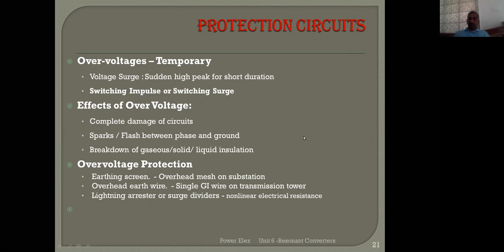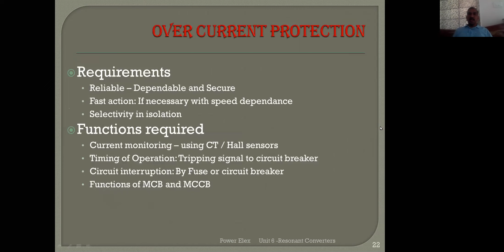The easier ways to protect are having an earthing screen, surge arresters, surge suppressors, lightning arresters, and an overhead earth wire. Along with the transmission lines, there is one metal wire just running on top, which is not carrying power. It is there so that whenever any lightning stroke occurs, it should not get in direct contact with the power line. Otherwise, the power line will carry that voltage to the appliances, which happens in some cases, and we hear it through news. So the overhead earth wire protects all such areas, attracting the lightning stroke and passing it through the tower directly to ground. Anything passed to ground takes the least resistance path, so other circuits are protected. This is how we generally protect against sudden overvoltage in circuits.